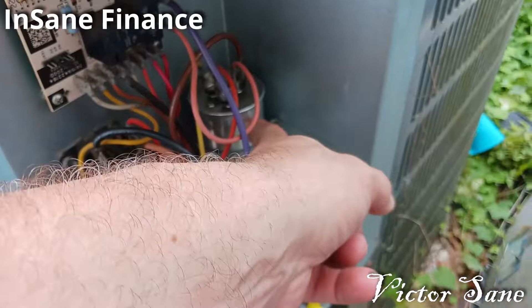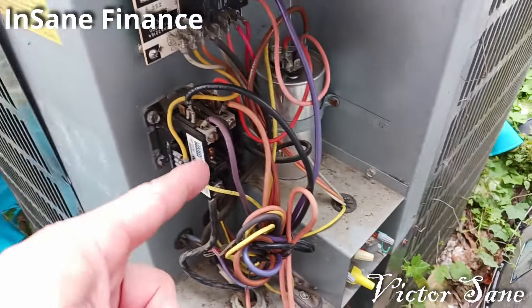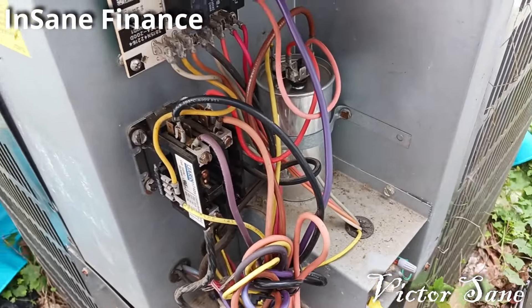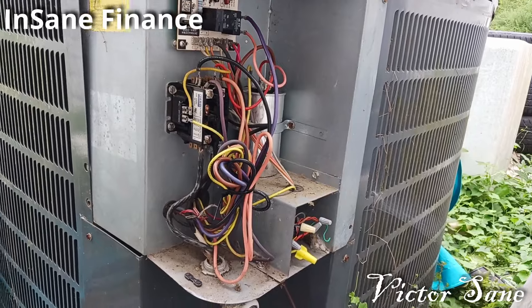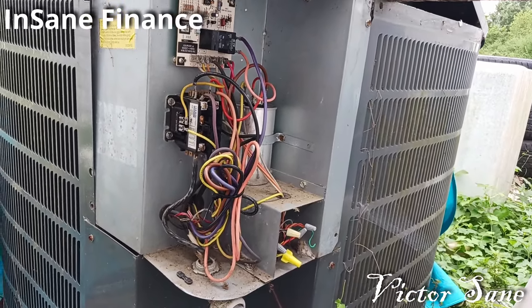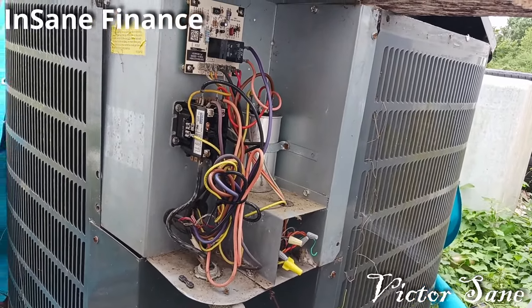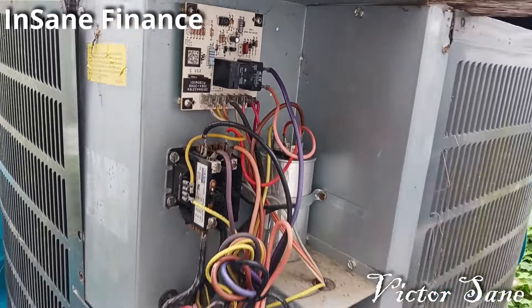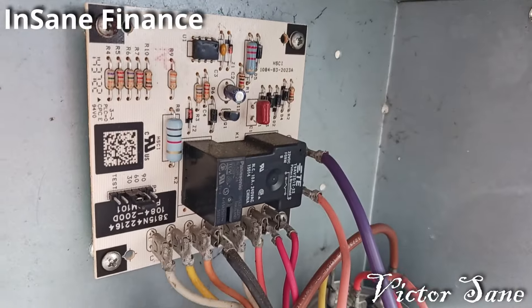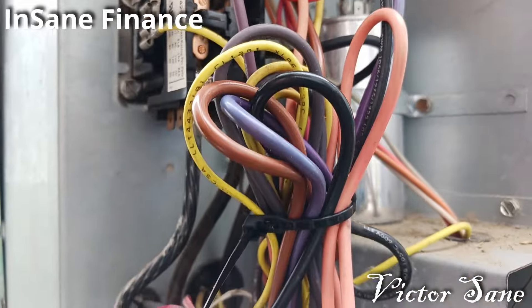I know this is more frequently going to be something like the start-run capacitor, but this time it was the contactor — bad contactor. I hope that helps you guys. Here's a pan back getting a good look at all the wires and where they go, in case you need to know or you've taken something loose and can't remember. I'll just pan down across it slowly in case you need to see.